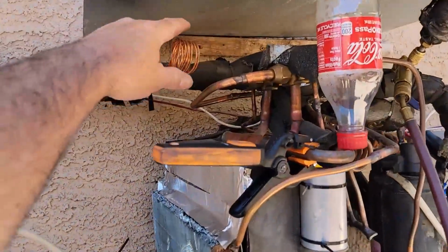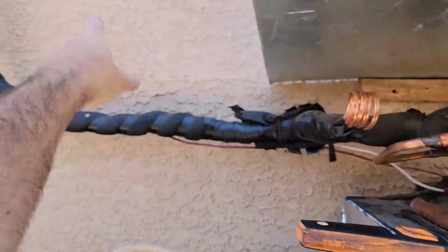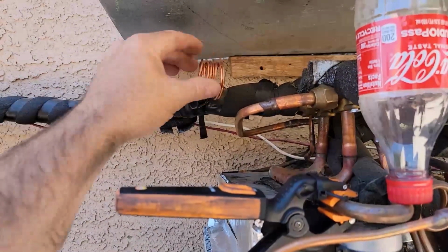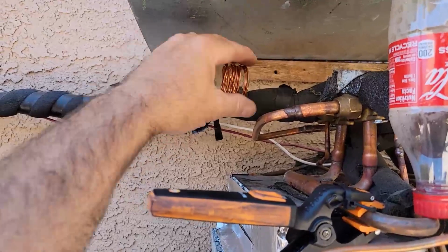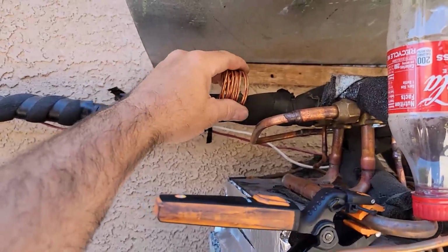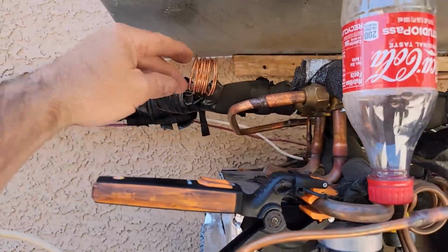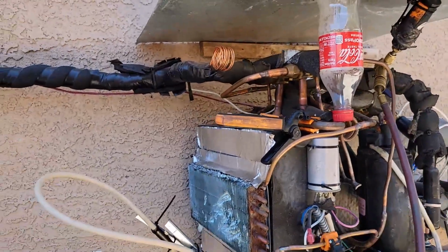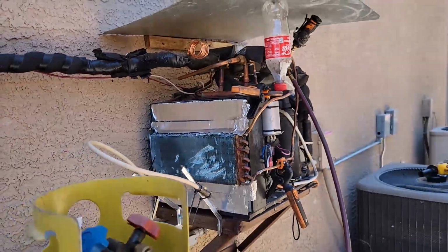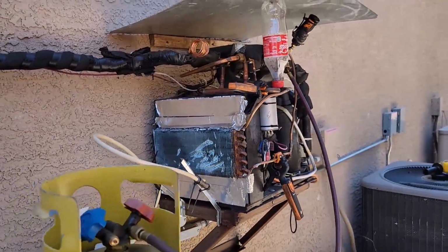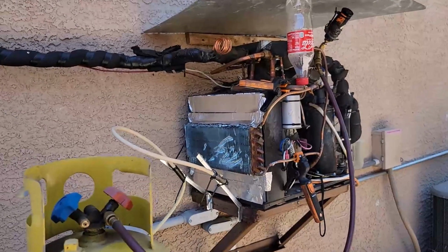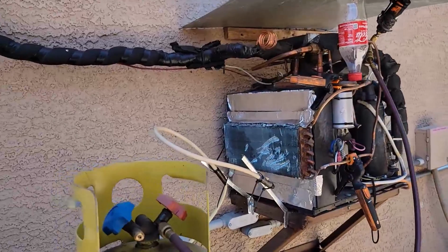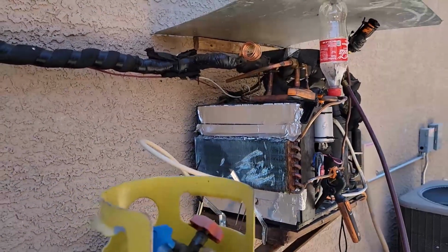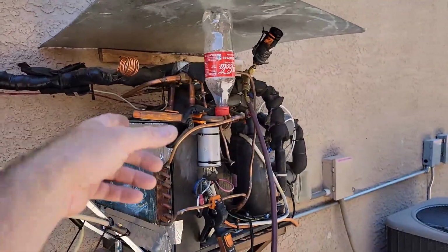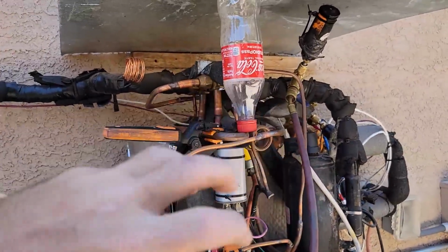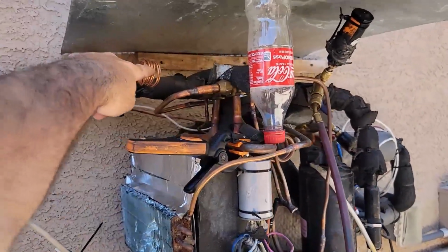What I calculate for this is like 1 ton, I think actually I have it a little less than that. These are just 2 capillaries in parallel. I've already had the system working great before it got hot out. So I actually like capillary tubes again. I'm preferring them over expansion valves on certain things, just because they work. They actually modulate a little bit. If this gets extra hot, a little bit of gas when you add it to the liquid just slows them down so it doesn't overfeed.